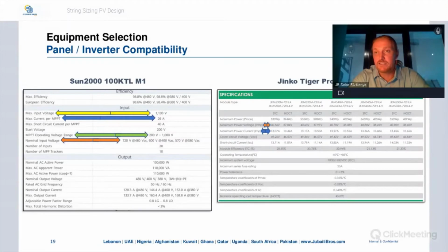Now, sometimes there are even larger panels, like 650 watts, and their max power current will be more than this, maybe 15 amperes. So if you're using a big panel that has a high max power current, you have to check the inverter and see if it can handle that. The very large panels are not made for these small inverters. We've seen this problem recently.